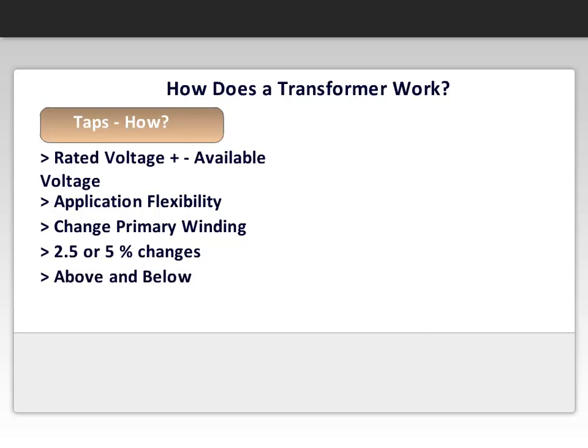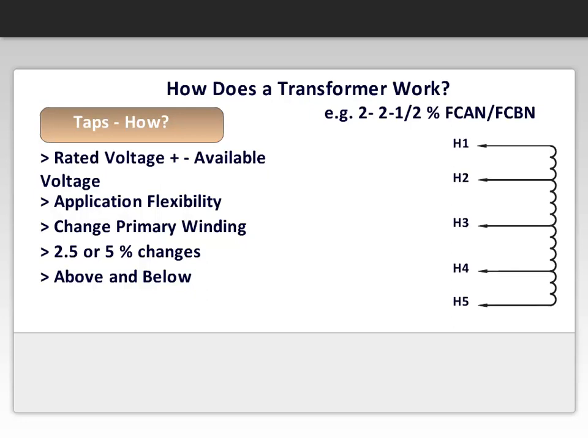Let's look at a standard dry type distribution transformer with two 2.5% taps above and two 2.5% taps below normal. The primary wiring diagram looks like this. Let's assume that the rated voltage is 480 volts. 2.5% of 480 would be 12 volts, making the above normal taps available at 492 and 504 volts.